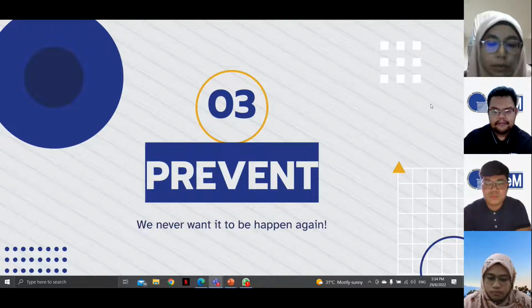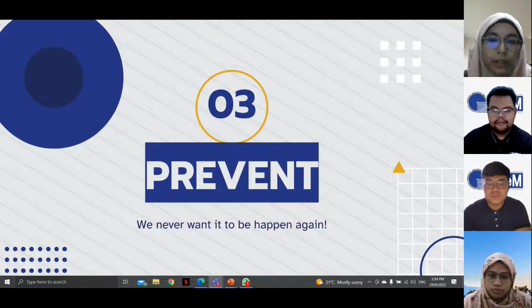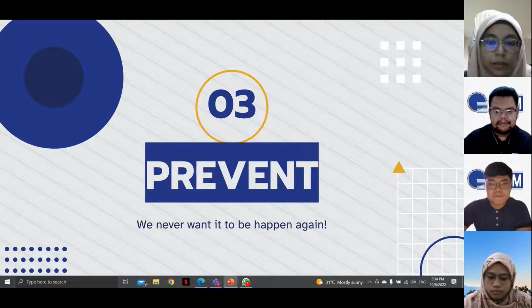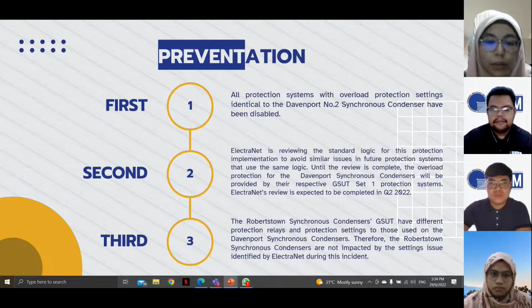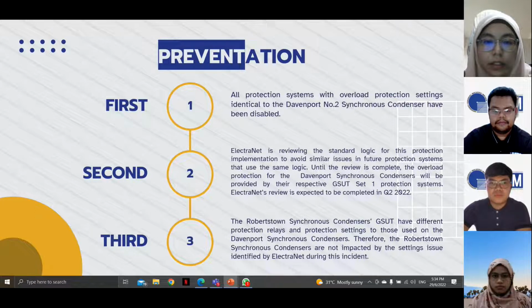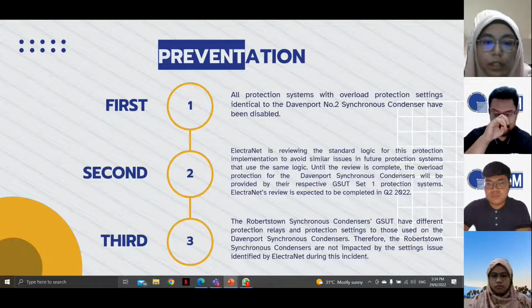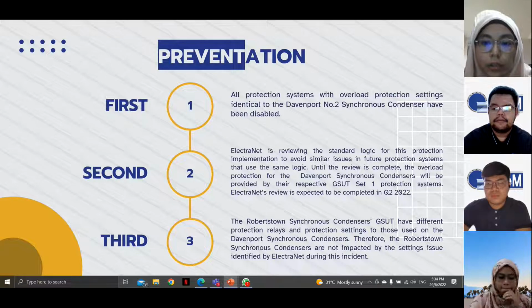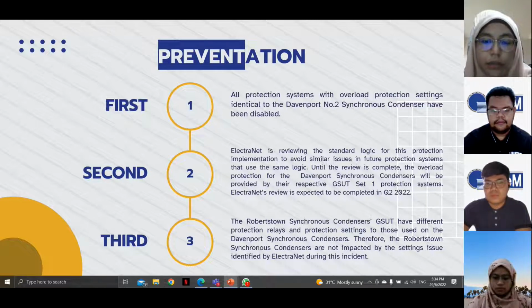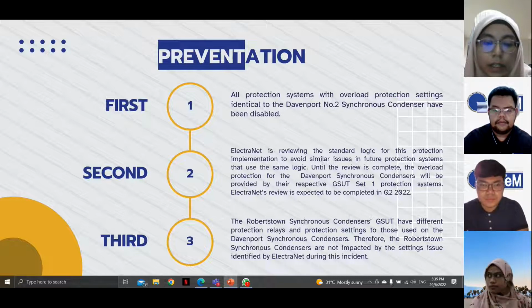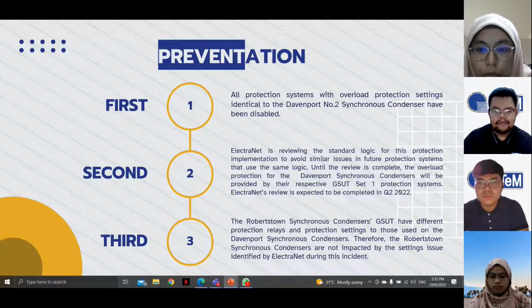For this slide, we want to prevent this accident from happening again. First, all protection systems with overload protection settings identical to the Davenport number 2 synchronous condenser have been disabled. Second, Electranet is reviewing the standard logic for this protection implementation to avoid similar issues in future protection systems that use the same logic. Until the review is complete, the overload protection for the Davenport synchronous condensers will be provided by their respective GSUT set 1 protection systems. The Electranet review is expected to be complete in Q2 2022.